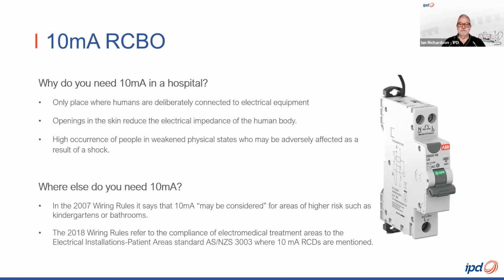So, Ian, we sometimes hear of 10 milliamp RCBOs being required in hospitals. Why is it necessary for 10 milliamp? Fred, a hospital is one of the only places where humans are deliberately connected to electrical equipment. There can be openings in the skin during operations that will reduce the electrical impedance of the human body. There's also a high occurrence of people in a weakened physical state, and this makes them more susceptible to being hurt as a result of a shock.